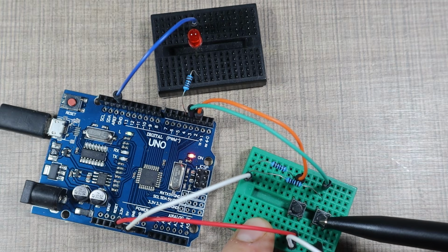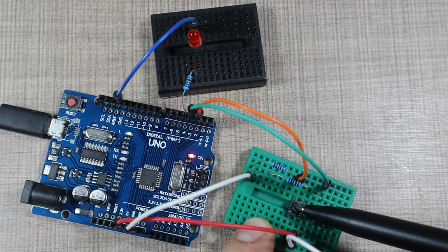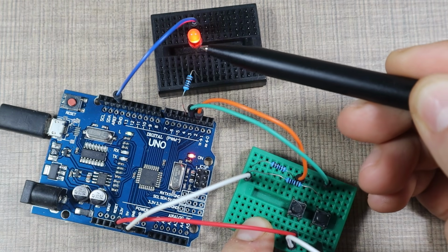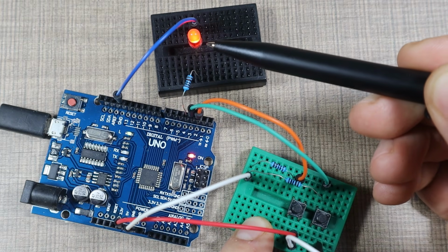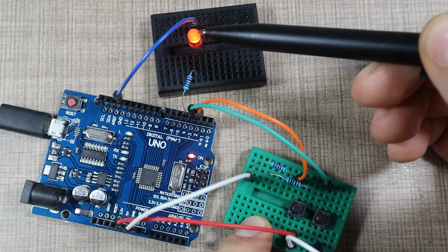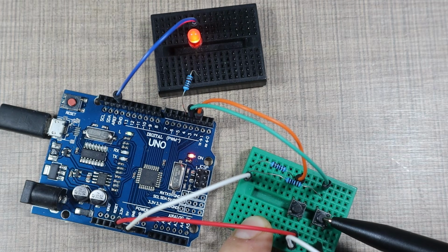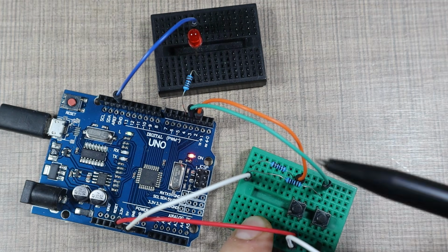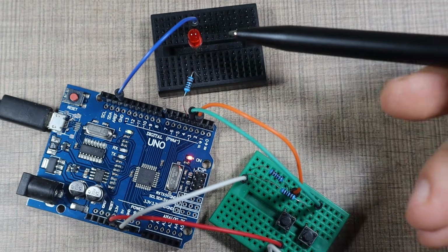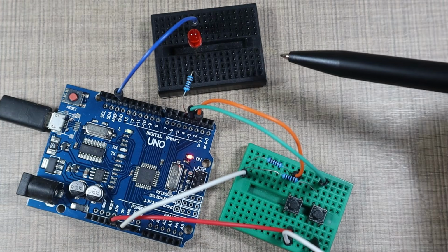If I press it, nothing really happens because the LED is already off. But if I press button 1, you can see that immediately the LED turns on, and this energizes our coil in exactly the same way as we had previously with the simulator, and that will stay on unless we press button 2 to reset the logic that we have. And keep in mind that this happens every 20 milliseconds because that's the default cycle that we have set here.